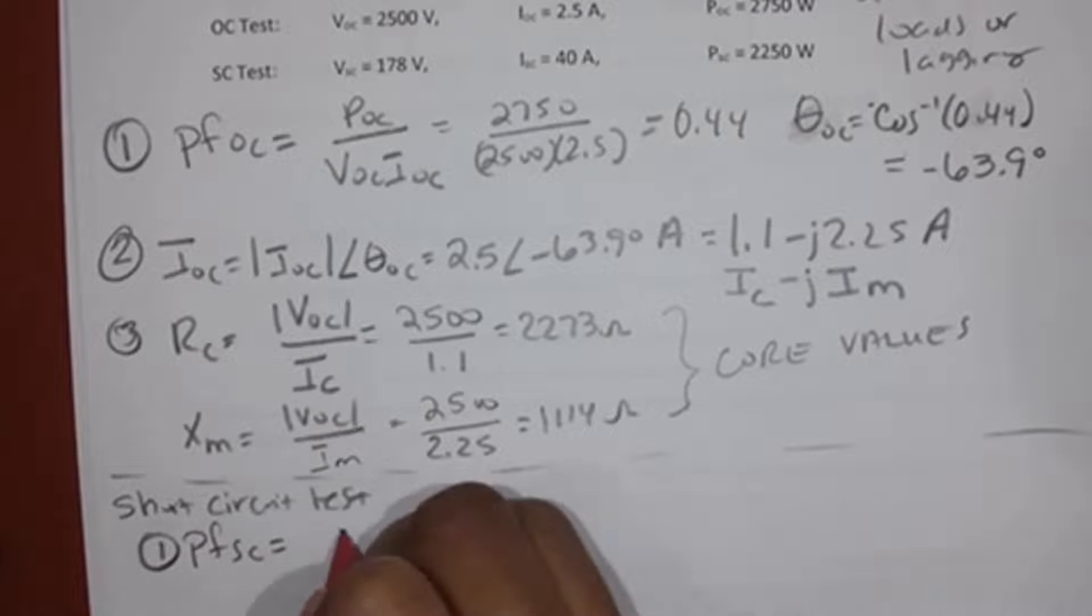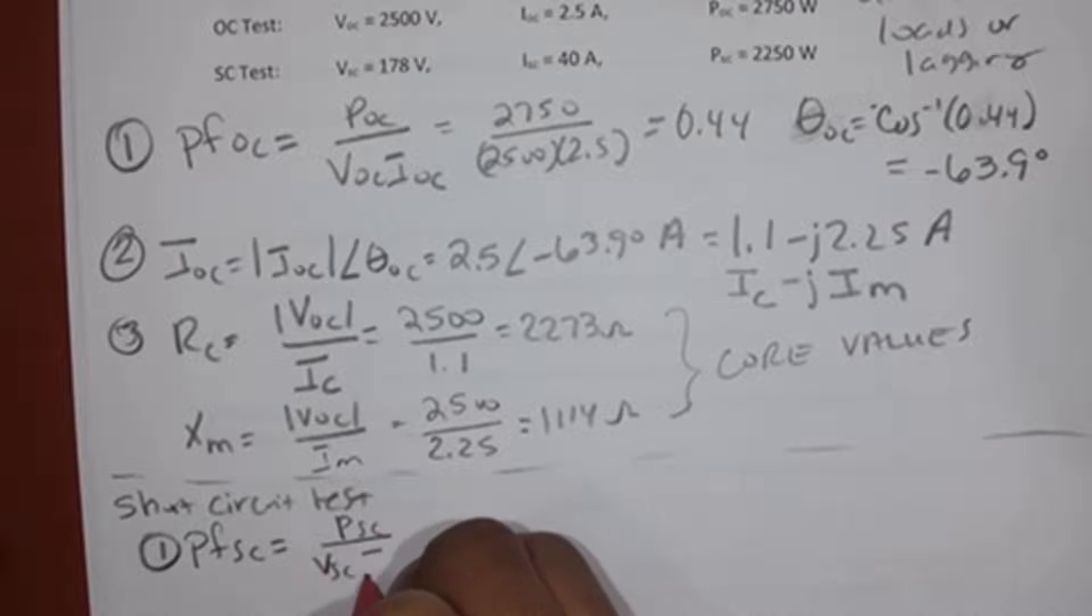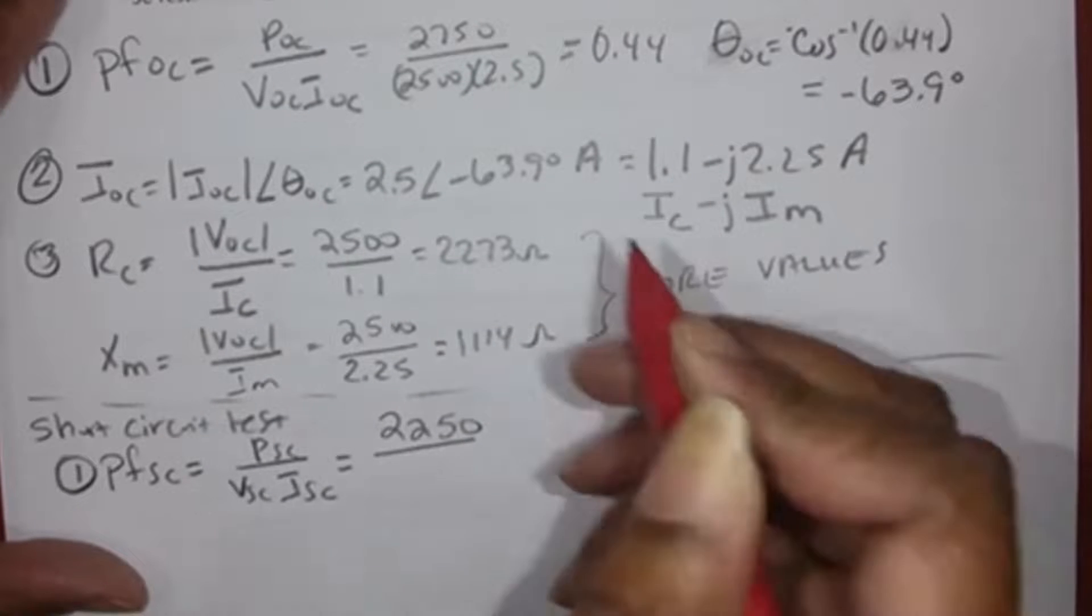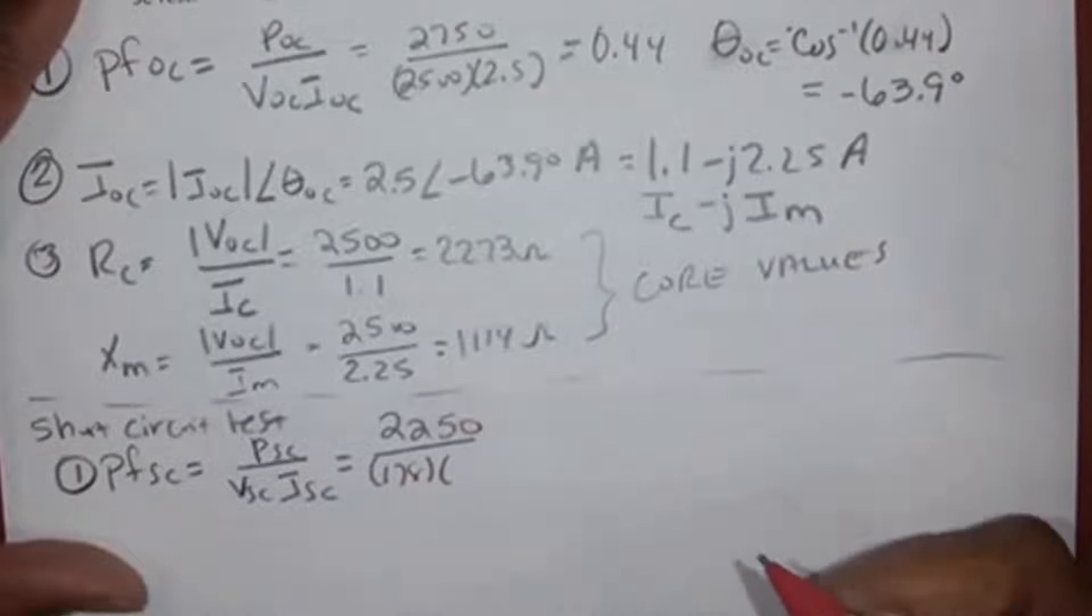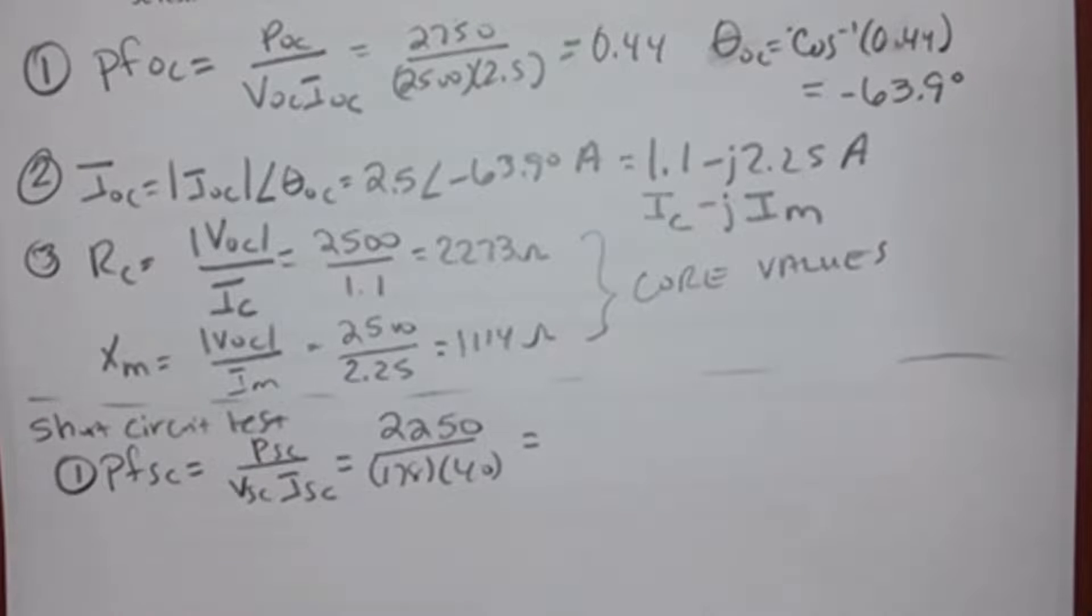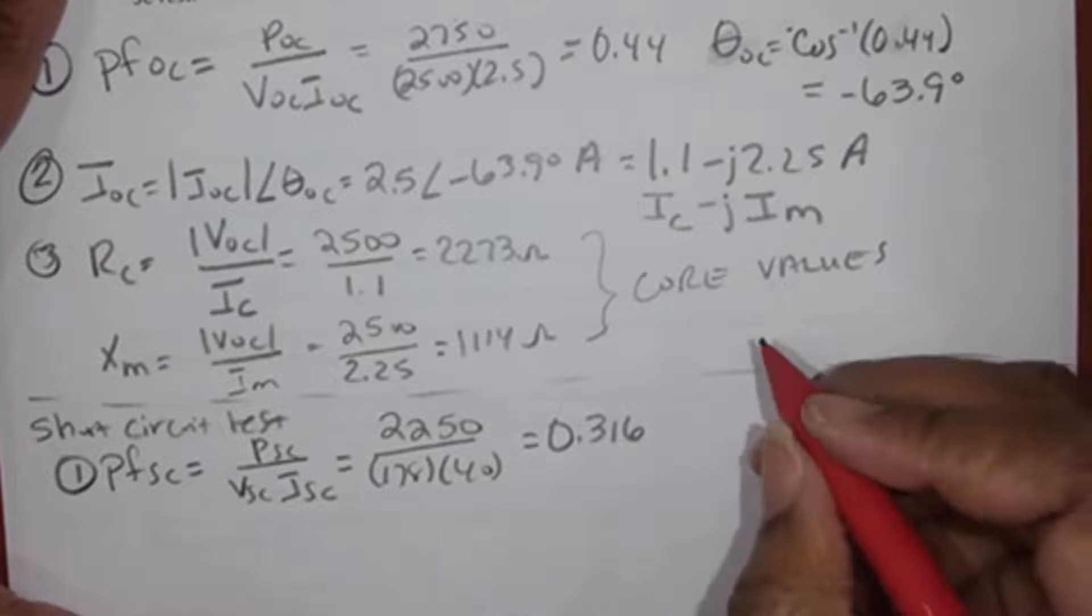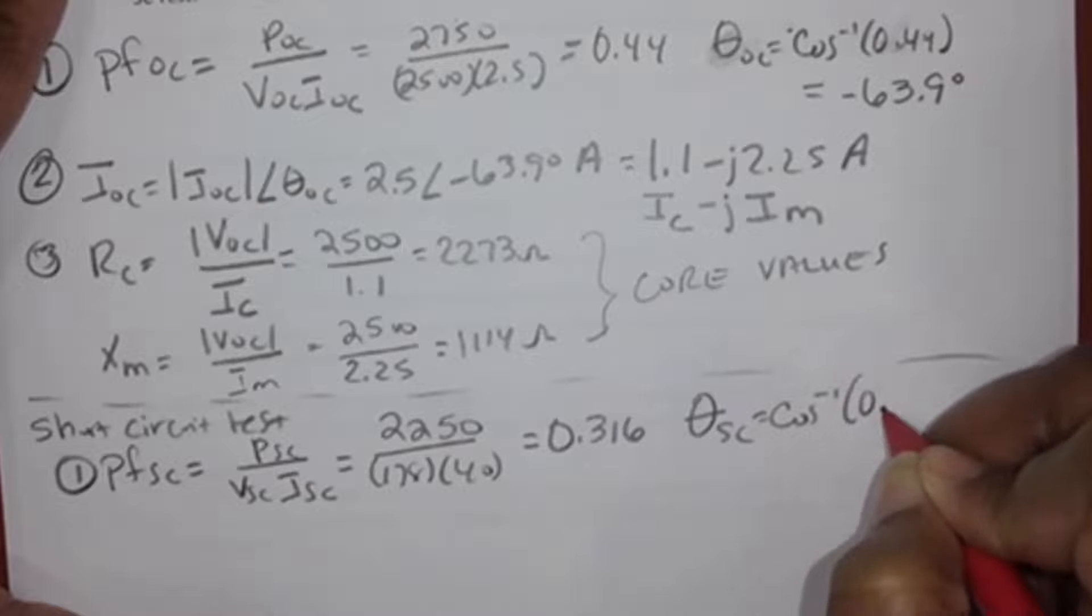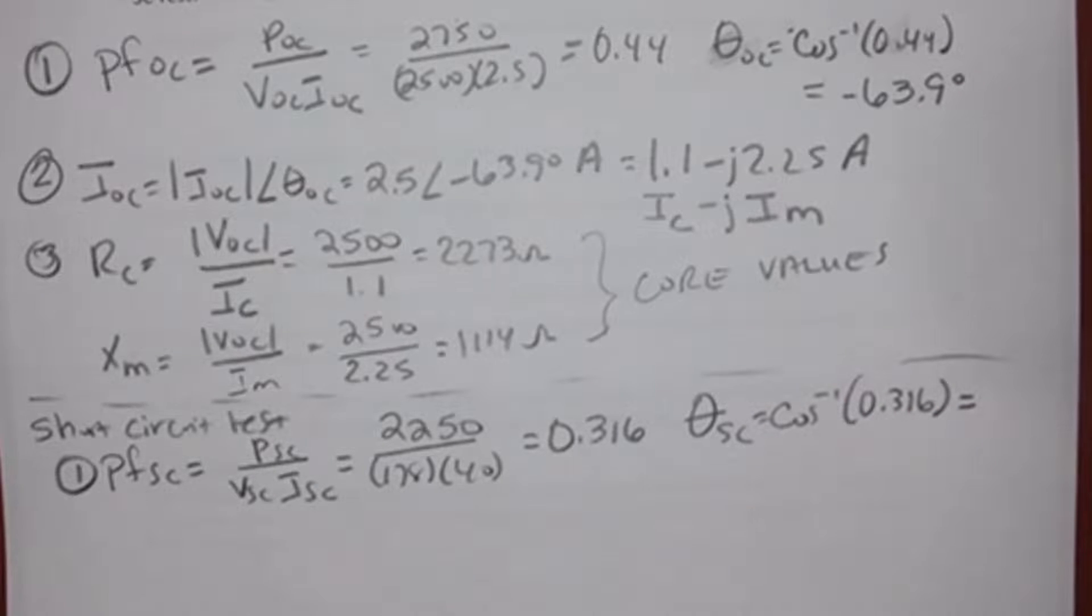So now I walk through those other three steps. Step one is to find PF short circuit. PF short circuit is going to be PSC over VSC times ISC. So that's going to be 2250 over 178 times 40. 0.316. Now find the arc cosine of that power factor. The arc cosine of 0.316 is 71.58 degrees.